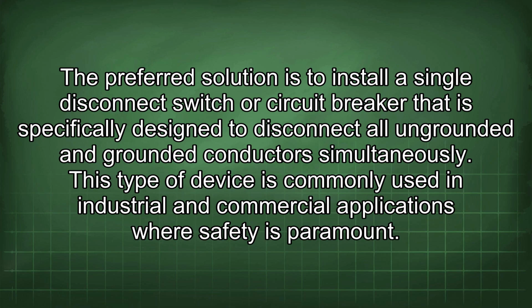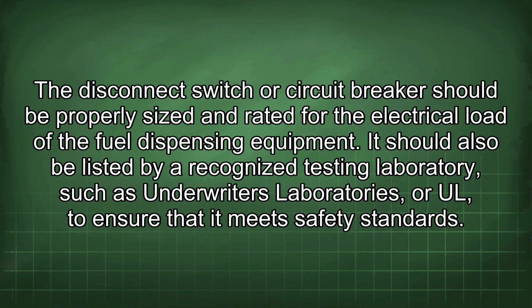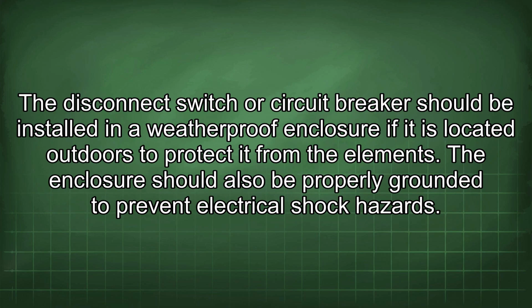The preferred solution is to install a single disconnect switch or circuit breaker that is specifically designed to disconnect all ungrounded and grounded conductors simultaneously. This type of device is commonly used in industrial and commercial applications where safety is paramount. The disconnect switch or circuit breaker should be properly sized and rated for the electrical load of the fuel dispensing equipment. It should also be listed by a recognized testing laboratory, such as Underwriters Laboratories, to ensure that it meets safety standards. The disconnect switch or circuit breaker should be installed in a weatherproof enclosure if it is located outdoors to protect it from the elements. The enclosure should also be properly grounded to prevent electrical shock hazards.